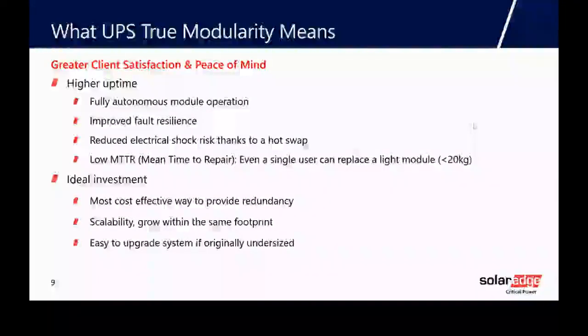What it means in summary is higher uptime, but most of all, it's greater client satisfaction and peace of mind. In the old days, when a UPS failed, we would get a very angry and concerned phone call saying your UPS is down, everything's gone down, it's a disaster, you must come in, you must come here within an hour. But now with modular systems, we just get a call saying one of the modules has gone down, come when you can to fix it. We've still got redundancy left on the other 10 modules in the system, so no stress. So it's very good for that.